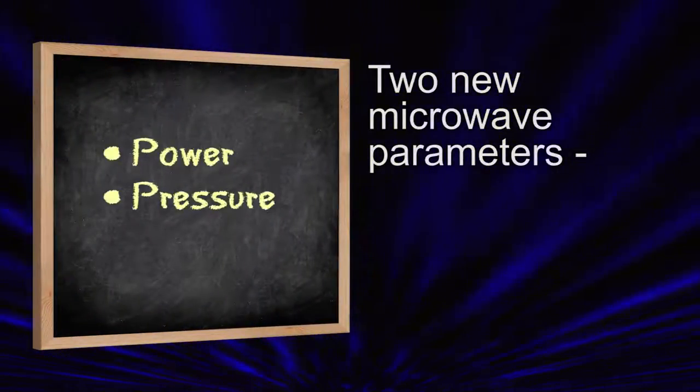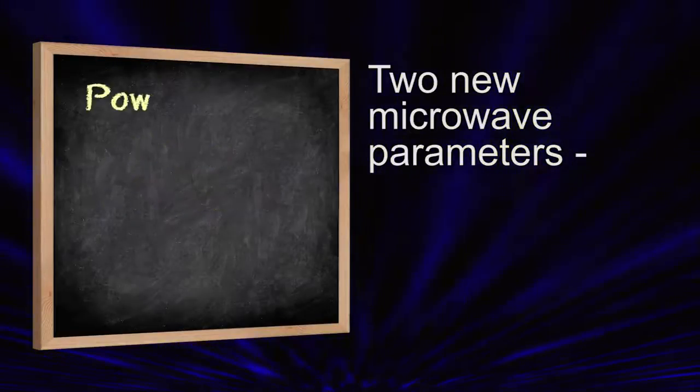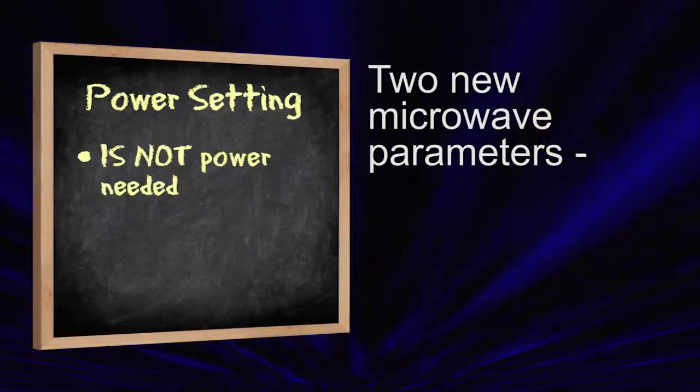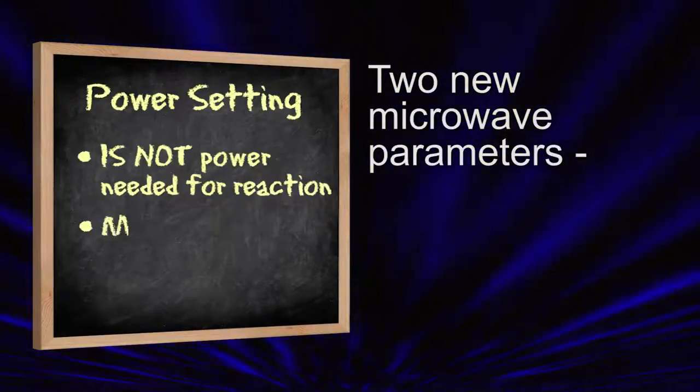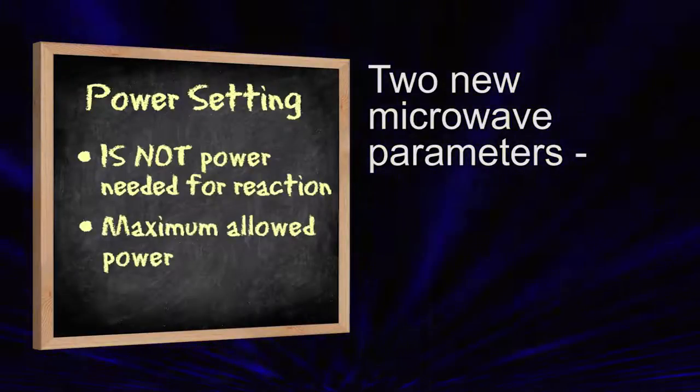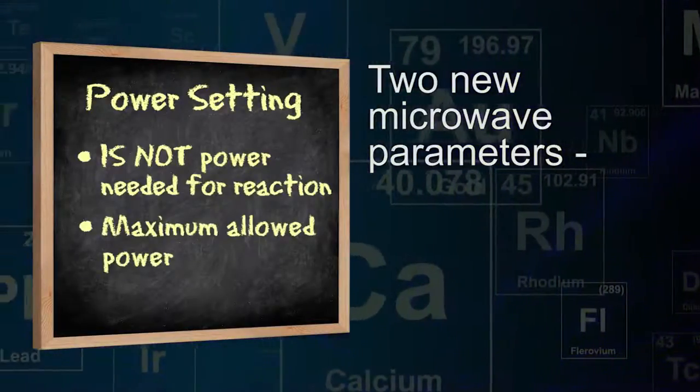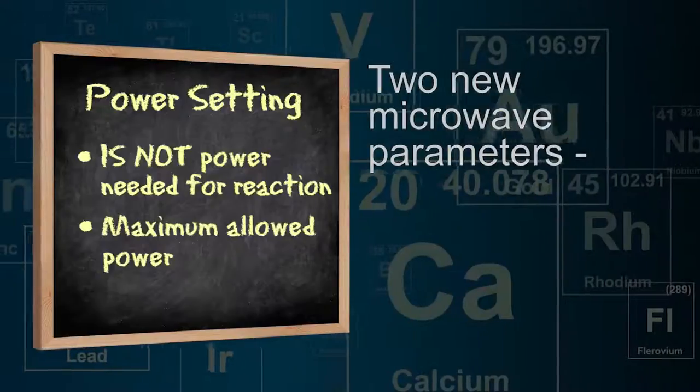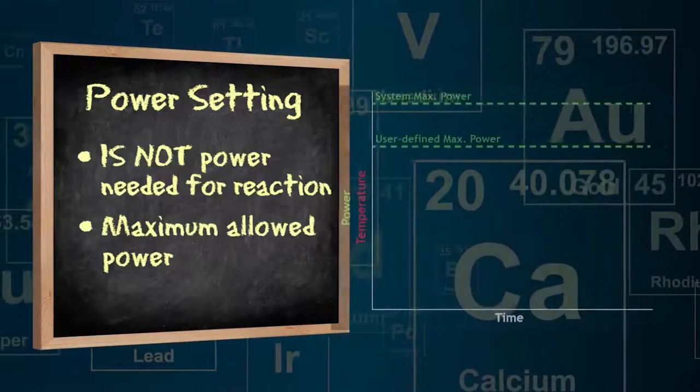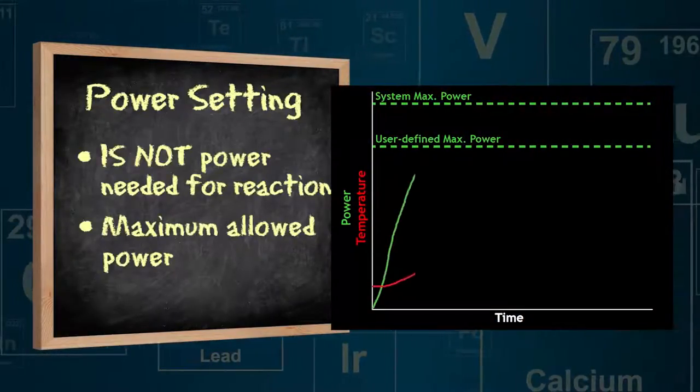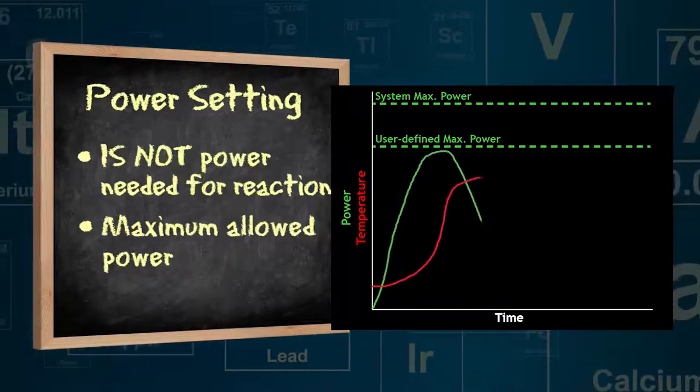Two new parameters to consider in microwave chemistry are the power and pressure settings. The power setting is not the amount of power used to heat a reaction, but rather the maximum allowed power. CEM's intelligent power control will automatically modulate the power output to heat a reaction solution to the desired temperature as quickly as possible without temperature overshoot and maintain that temperature.